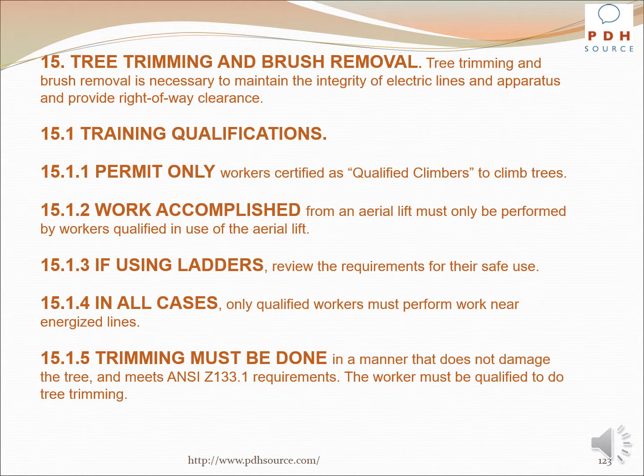With regard to tree trimming and brush removal operations, tree trimming and brush removal is necessary to maintain the integrity of electric lines and apparatus and provide right-of-way clearance. Permit only workers certified as qualified climbers to climb trees. Work accomplished from an aerial lift must only be performed by workers qualified in use of the aerial lift. If using ladders, review the requirements for their safe use. In all cases, only qualified workers must perform work near energized lines.